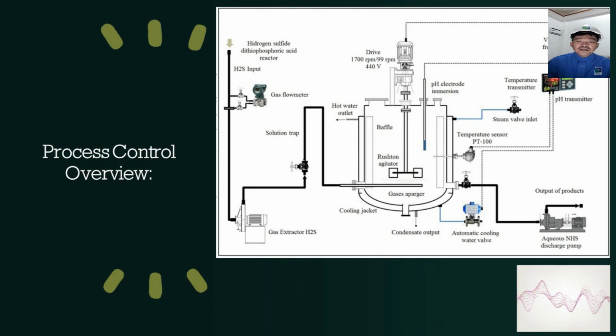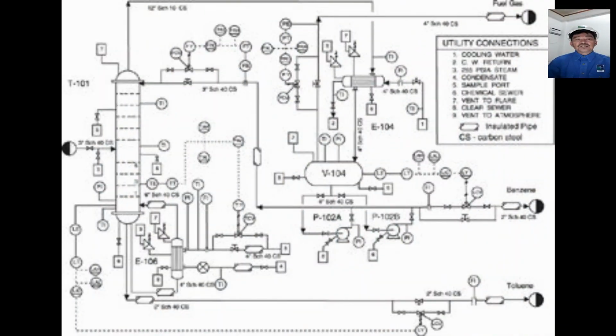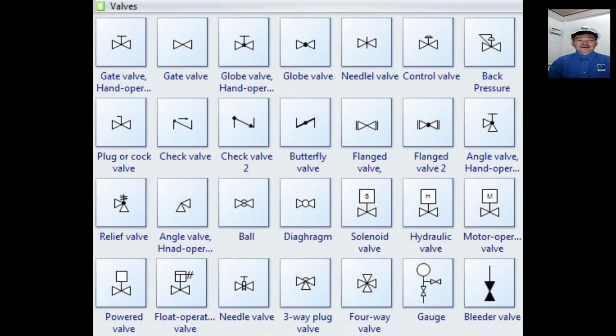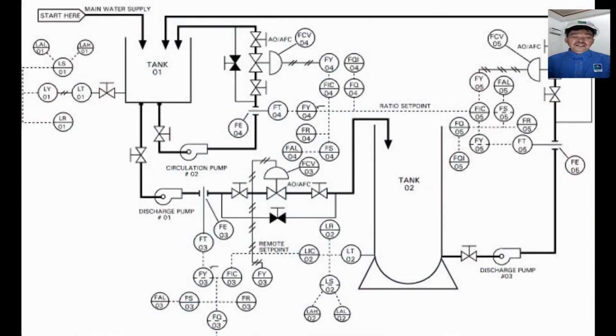This picture shows a piping and its installed process instrumentation. These are the instruments normally found in the P&ID. P&ID stands for Piping and Instrumentation Diagram. Looking at the P&ID, you will see all the installed instrumentation related to the piping, and other process information like the process flow or flow direction is indicated as well. The service equipment, line number, process line, associated equipment, and other information can be found in the P&ID. Understanding the P&ID is essential for an instrument engineer, as well as reading symbols and other standard terminologies that you have to know in P&ID.